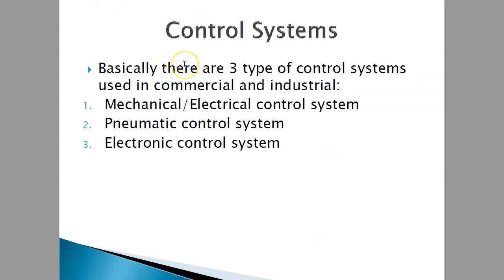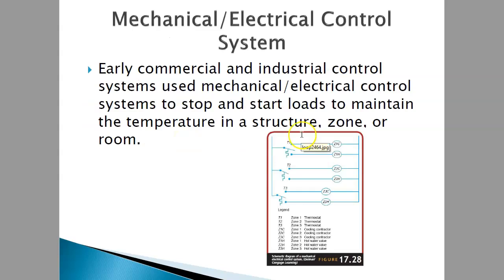Control systems: basically, there are three control systems used for commercial and industrial applications. They are mechanical/electrical, pneumatic, and also electronic control systems. In the early stage, mechanical or electrical control systems were used to stop and start the loads to maintain the temperature in the structure, zone or room. Here we could see the mechanical or electrical control system components: thermostat, cooling contactor, and hot water valve.